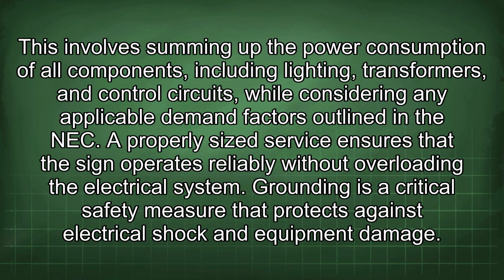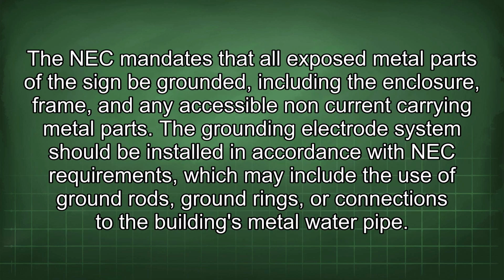Grounding is a critical safety measure that protects against electrical shock and equipment damage. The NEC mandates that all exposed metal parts of the sign be grounded, including the enclosure, frame, and any accessible non-current carrying metal parts. The grounding electrode system should be installed in accordance with NEC requirements, which may include the use of ground rods, ground rings, or connections to the building's metal water pipe.